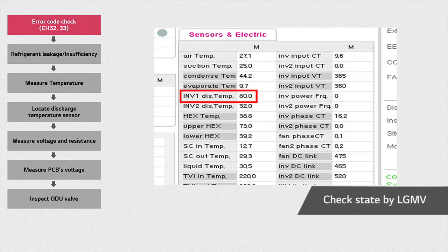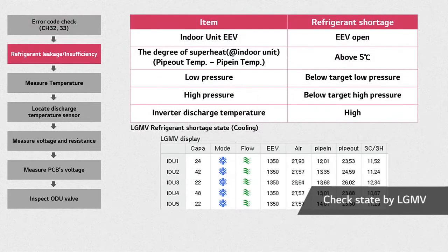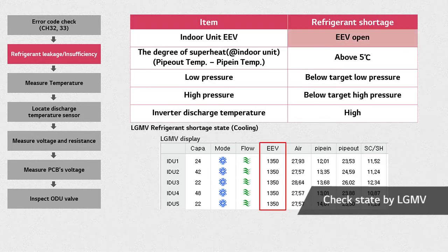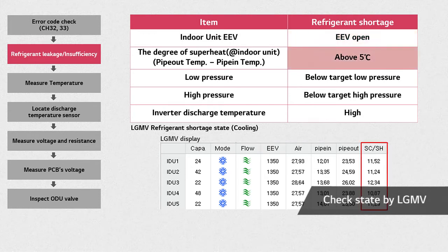Check the discharge temperature using the data from LGMV. To solve this problem, start by checking if the refrigerant is insufficient using LGMV. Through LGMV, you can also check the cycle. You can tell that the refrigerant amount is insufficient when the indoor unit EEV is fully open and the degree of superheat at the indoor unit is above 5 degrees.